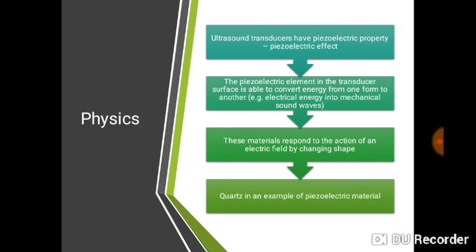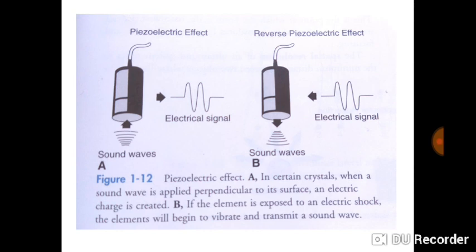The major element present in the transducer is the piezoelectric element. These elements have the ability to convert energy from one form to another — in the case of ultrasound, electrical energy into mechanical sound waves. When reflection of sound takes place in the body, the same element converts it back into electrical signals, which is what you see as a display on the ultrasound screen. This is called the piezoelectric effect.